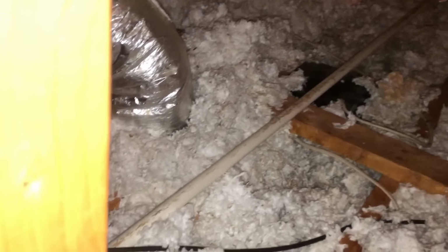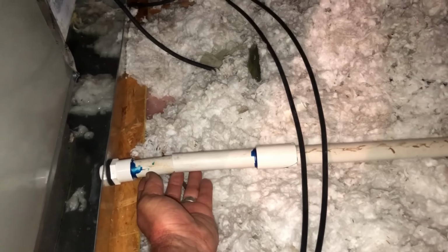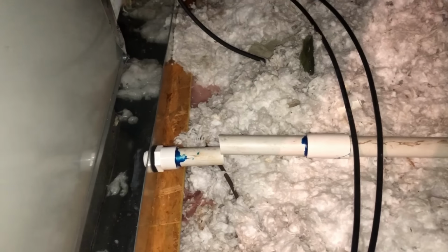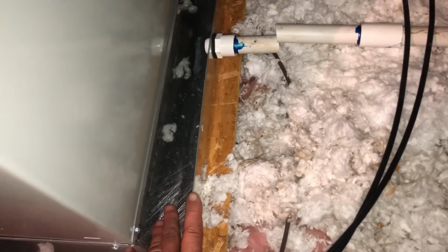So to get that laying level, or to where it has fall all the way out, I think it would have to be up like that. So what must have happened before the change out was done is, because this is a newer unit, the pan before probably sat up on blocks. And that's probably why there are those 2 4-inch solid blocks left over there.